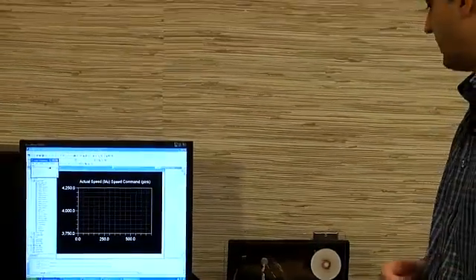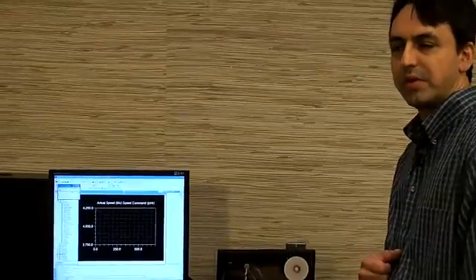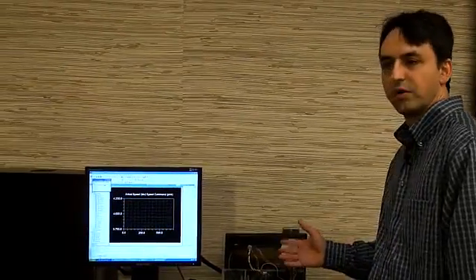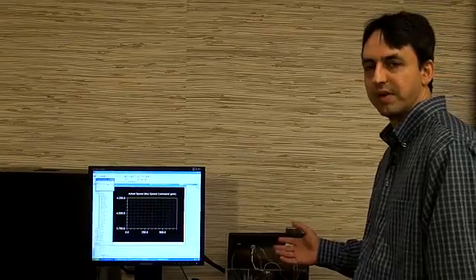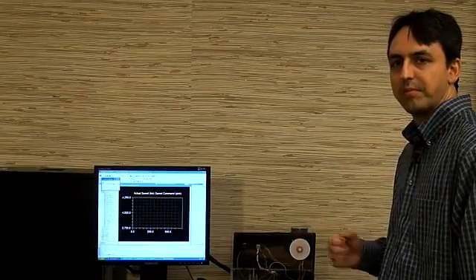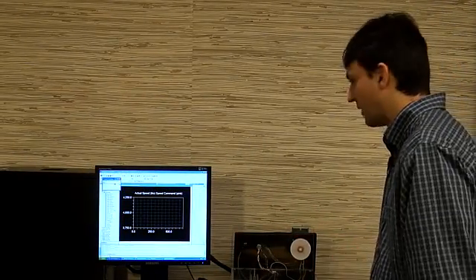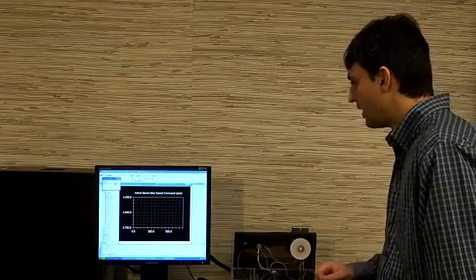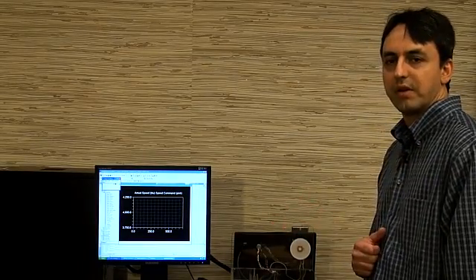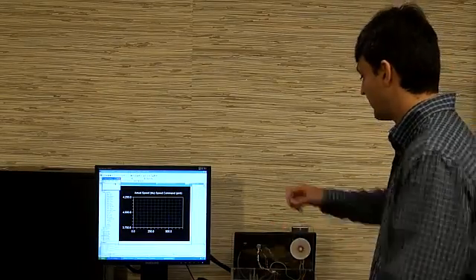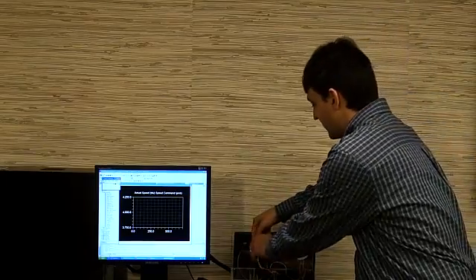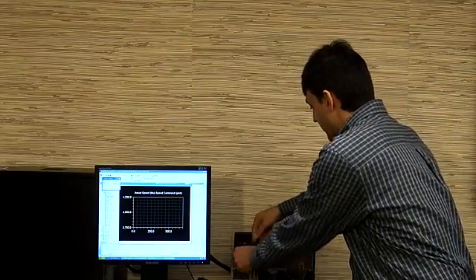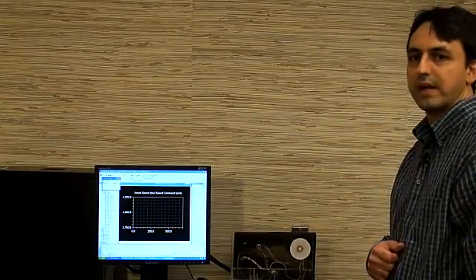What this demo also allows me to do is to switch over from sensored control using the encoders as feedback to sensorless control, which I will do right now. Now I am running in sensorless mode, and to prove that I will disconnect the encoder cables. The motor continues to run without a hitch.